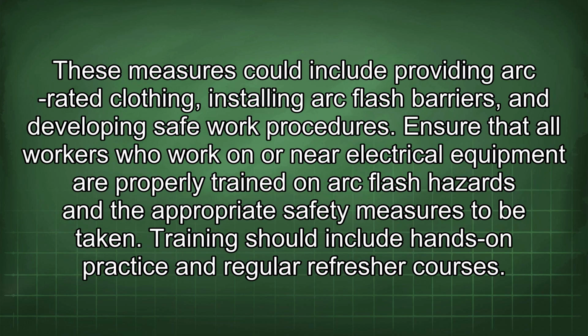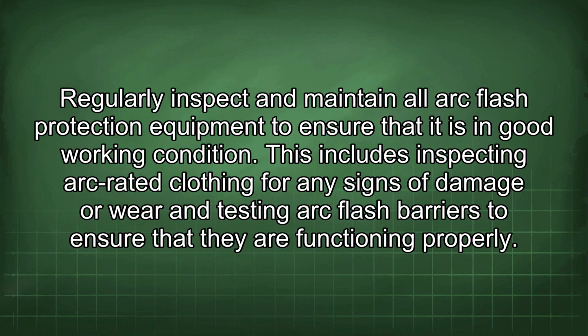These measures could include providing arc-rated clothing, installing arc flash barriers, and developing safe work procedures. Ensure that all workers who work on or near electrical equipment are properly trained on arc flash hazards and the appropriate safety measures to be taken. Training should include hands-on practice and regular refresher courses. Regularly inspect and maintain all arc flash protection equipment to ensure that it is in good working condition. This includes inspecting arc-rated clothing for any signs of damage or wear and testing arc flash barriers to ensure that they are functioning properly.